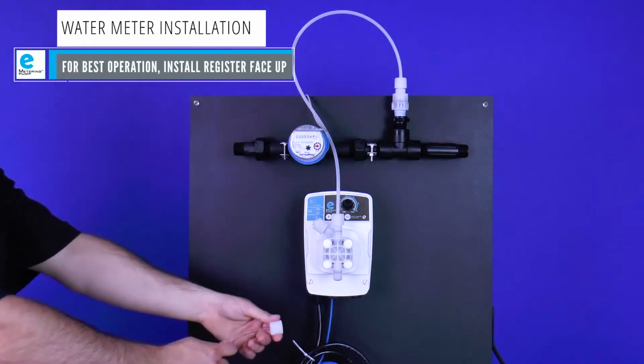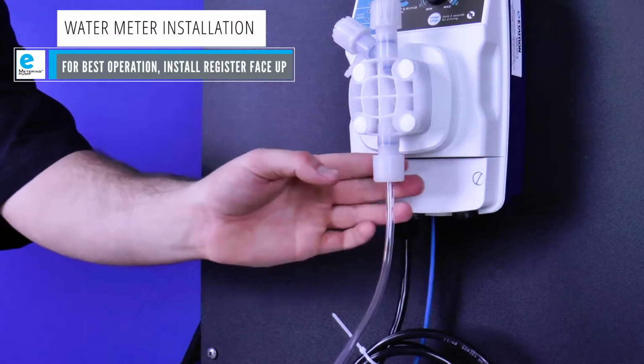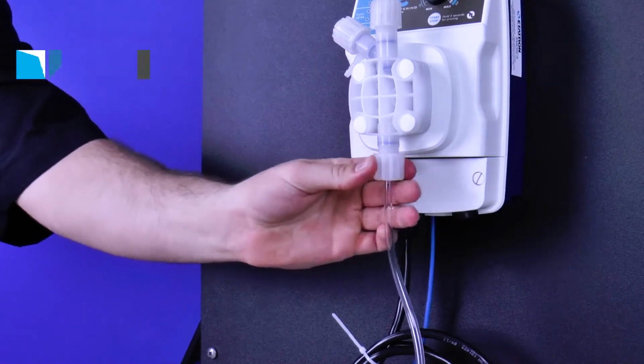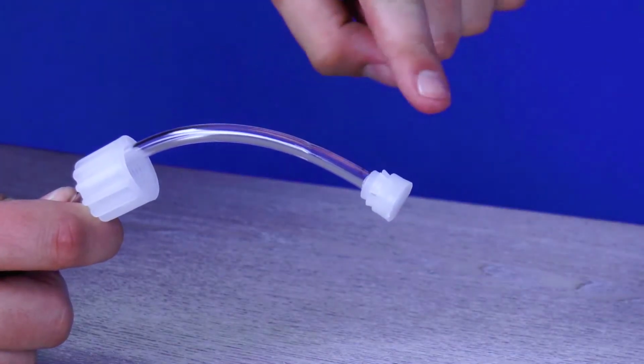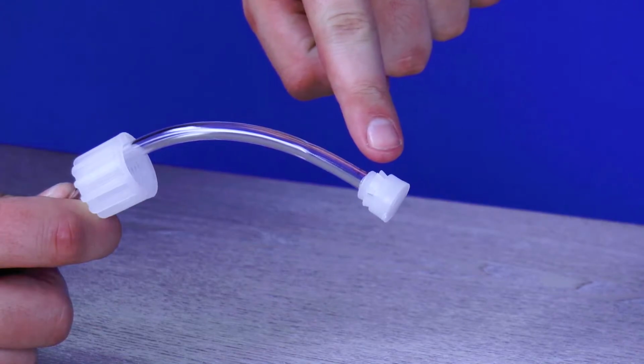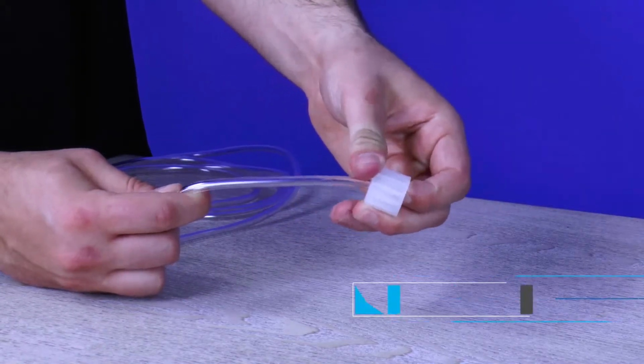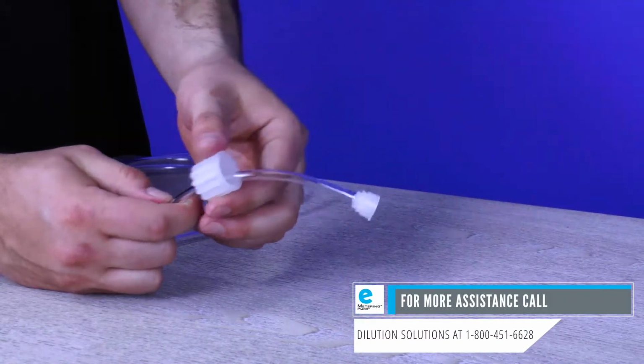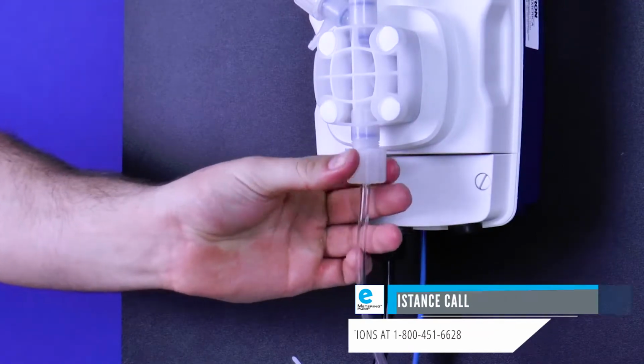Attach the tube and tube connections onto the suction valve by hand tightening the tube nut. Do not cross-thread nor over-tighten. If the tube nut is not securing, recheck the ferrule connection. Pull the tube nut toward the nozzle once more to compress the collar and nozzle together. Retighten the tube nut until secure.